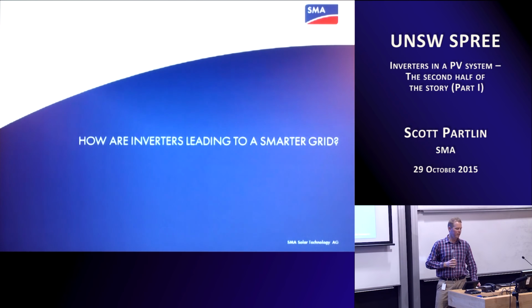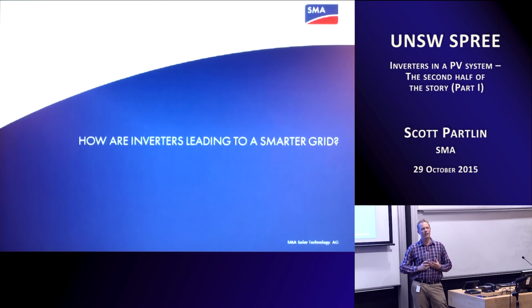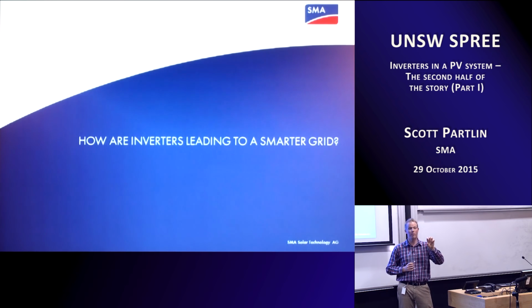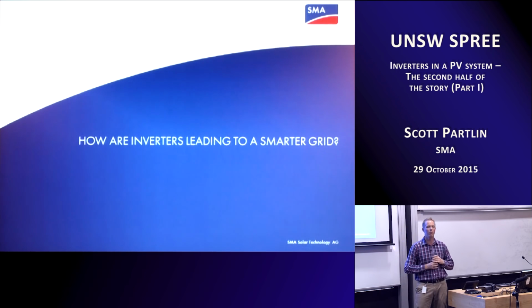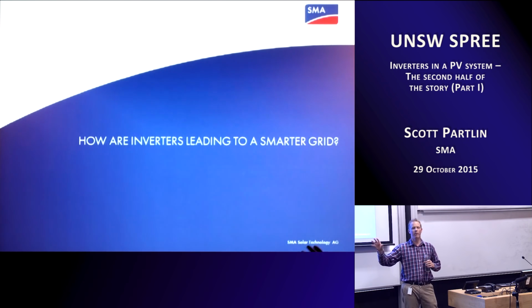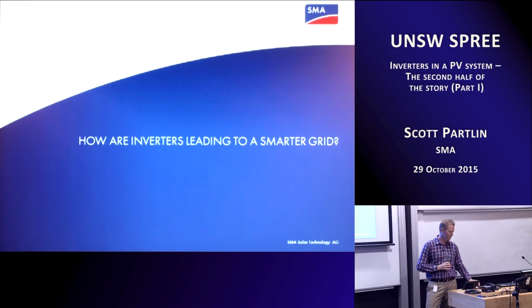It's that functionality that is probably really important now, because as solar becomes ever more prevalent in the grid, the ability of our electric power grid to cope with that solar is being tested. We have electric power grids around the world that were designed pretty much 50 years ago. They had a design principle of centralised generation, high voltage transmission, some medium voltage consumption, medium voltage transmission, and then consumption at the low voltage grid, which is what these lights are all plugged into. So they were never designed to have energy generation at the other end, pushing it all the way back up that flow.